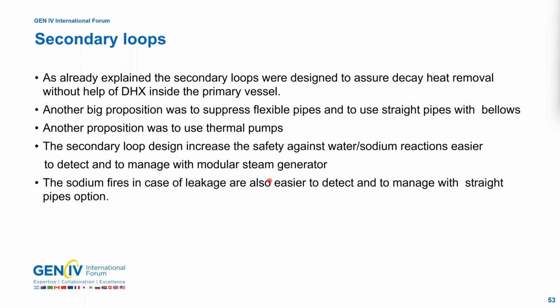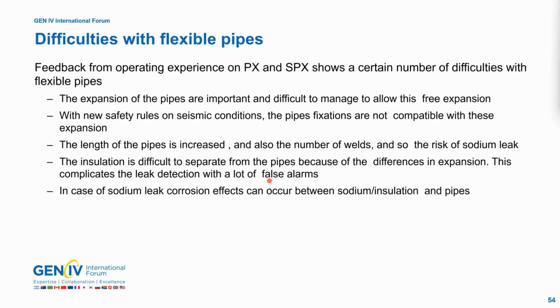So we arrive now at the secondary loops. We have seen the primary circuit. We have seen the DHRS system. Now we arrive at the improvements of the secondary loops. The secondary loops are designed to assure the decay heat removal, but the big proposition for the secondary loops was to suppress the flexible pipes and to use straight pipes with bellows. Another proposition was to use thermal pumps. The secondary loops design increases the safety against water-sodium reactions because with the modules, these reactions are easier to detect and easier to manage with a modular steam generator. Sodium fires in case of leakage are also easier to detect in the new disposition and to manage with the straight pipe options, and we will see that later.